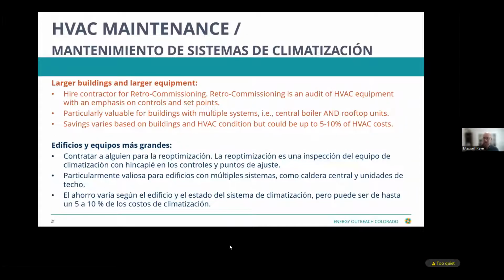A lot of times we'll have maintenance folks or property management go in and fine tune or adjust set points for different conditions or different complaints in the building. Sometimes we'll have tenants let themselves into the HVAC equipment and start making adjustments based on their preferences. And all those little adjustments over time can really diminish the performance and efficiency of your HVAC equipment. So a retro commissioning audit is essentially a full assessment by a third party of how your HVAC equipment performs, and again, we're talking about bigger equipment here. I'm thinking 20 units plus, rooftop units, central boilers, more complicated systems perhaps.